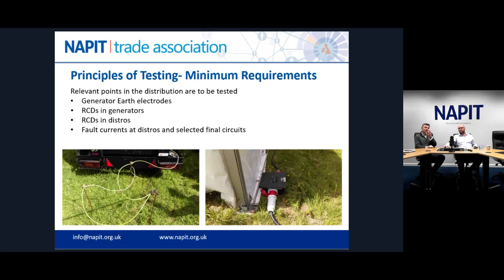And also, it's important to do a few checks on final circuits and some distribution circuits. As we pointed out earlier, because all the equipment is tested, we don't necessarily have to test all of the distribution, and that's where BS 7909 has a modified testing regime to take this into account. If you imagine an ordinary 4-way block of 13 amp sockets, if you test one outlet, then you can reasonably assume that you're going to get similar numbers on the other outlets if that extension lead has been tested before it came out from the warehouse.